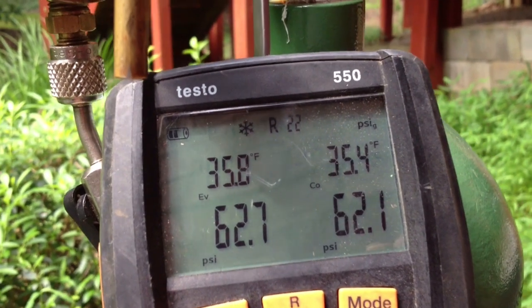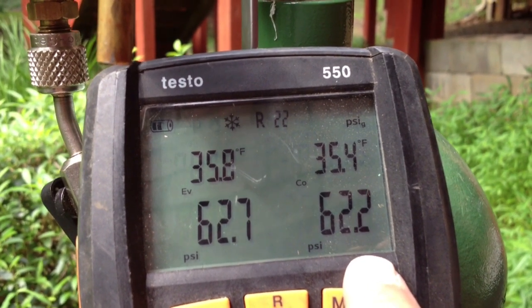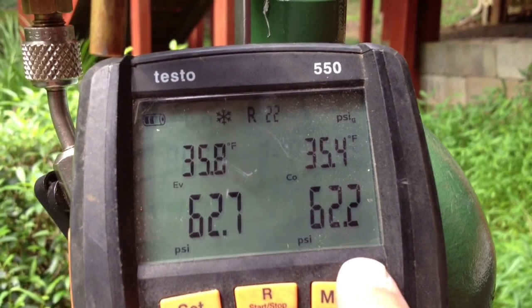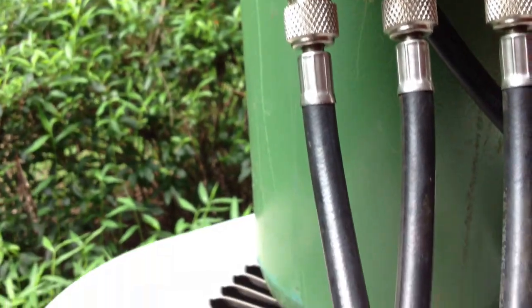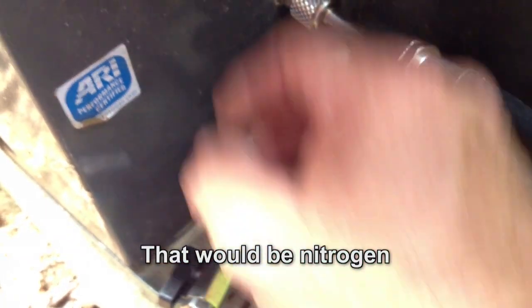We started off at 62.7 on the low side, 62.5 on the high side, and you can see it's dropped down and hasn't gone up — all the way down to 62.2, and eventually it'll be 62.1 and keep dropping. What I did was close the liquid side and the suction side valve off, and pumped an equal amount of nitrogen into both sides. So I've got my low side on my unit and my high side on the line set side.